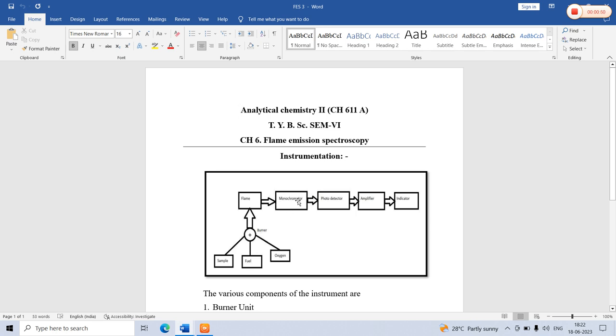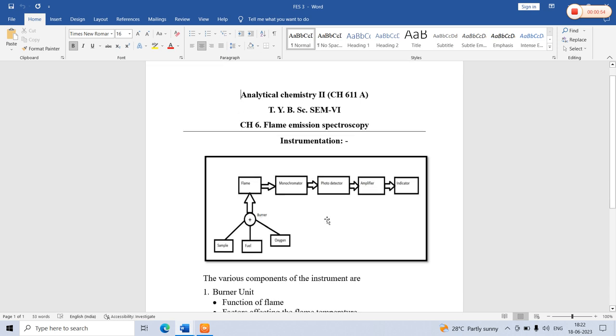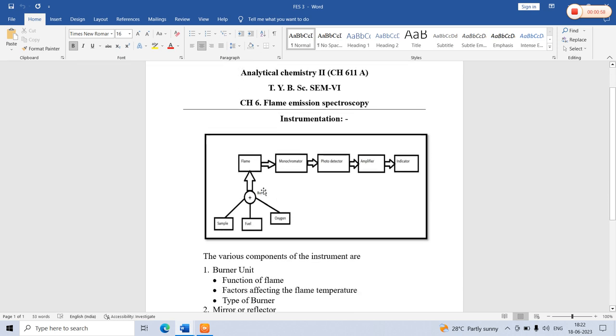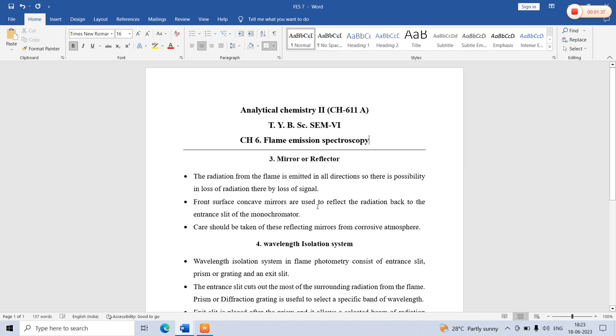In this lecture, we will focus on the monochromator system. The instrumentation block diagram for flame emission spectroscopy consists of the burner head, flame, monochromator, photo detector, amplifier, and indicator. The amplifier and indicator constitute the signal readout device. The detector used in flame emission spectroscopy is the photomultiplier tube. Now we will focus on the role of the monochromator and the wavelength isolation system.